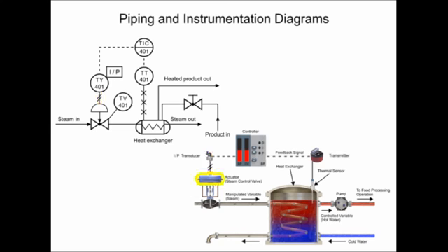The pneumatic control diaphragm actuator that opens and closes the globe valve regulates steam in the process. The actuator is represented by the half circle in the P and ID. The arrow pointing downwards from the actuator indicates a fail-closed valve type.